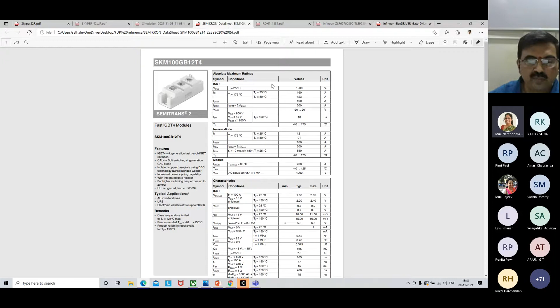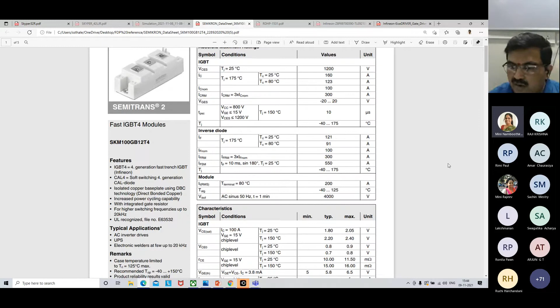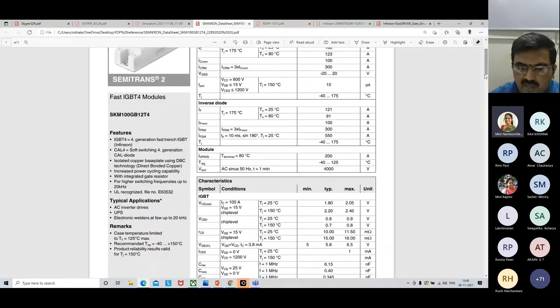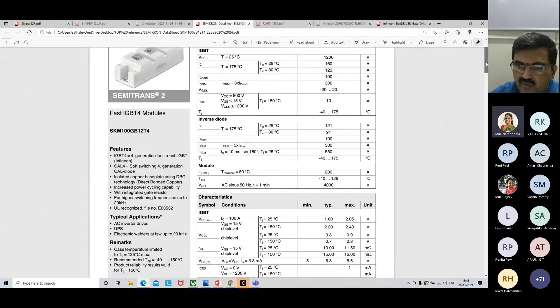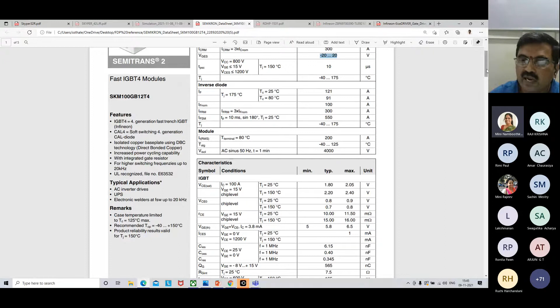Now let's take the SEMIKRON IGBT module, model 100 GB 12T4, and try to match it with our Skyper 32. The specification is 1200 volts, 160 ampere peak, average current at 25 degrees Celsius. VGS is minus 20 to plus 20 volts—plus/minus 20 volts is the maximum voltage. It should never happen that under fault conditions the gate voltage goes beyond 20 volts, otherwise the gate gets damaged.